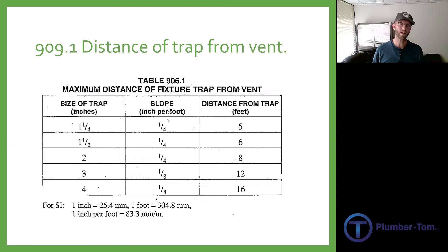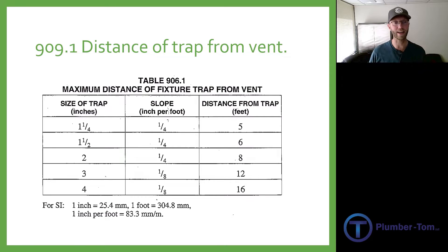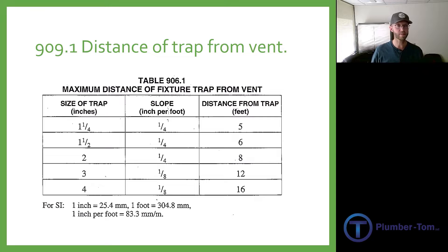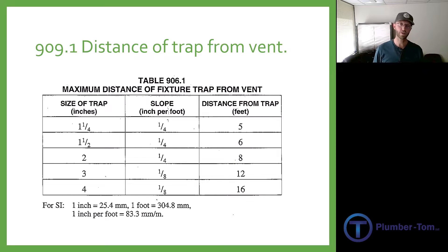Section 909.1 — we look at distance from the trap vent. This is one you need to memorize. On table 906.1, we have a list of trap sizes from one and a quarter up to four inches. The slope coordinates directly with chapter seven. We have quarter-inch per foot all the way up to two-inch pipe, and then eighth-inch per foot for the three and four inch. Then we have distances from the trap: five feet for an inch and a quarter.